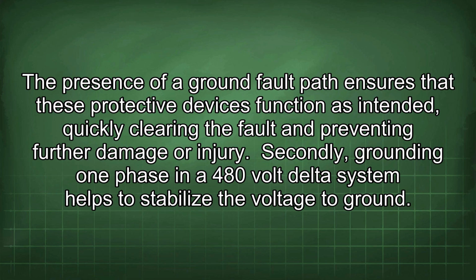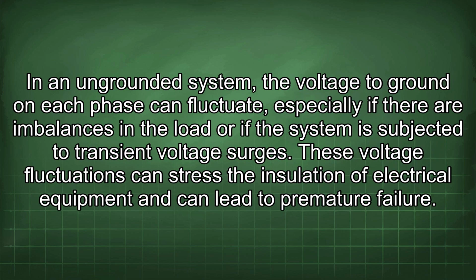Secondly, grounding one phase in a 480-volt delta system helps to stabilize the voltage to ground. In an ungrounded system, the voltage to ground on each phase can fluctuate, especially if there are imbalances in the load or if the system is subjected to transient voltage surges. These voltage fluctuations can stress the insulation of electrical equipment and can lead to premature failure.